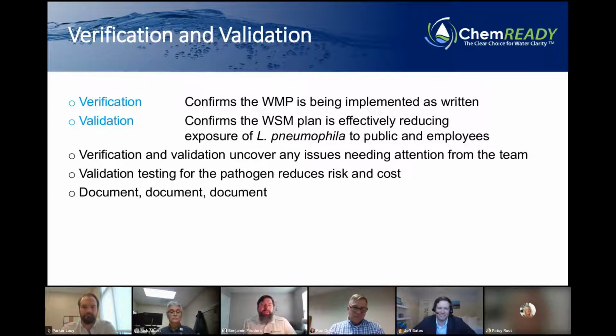That brings us to verification and validation. I wanted to remind everyone what that means. In ASHRAE 188, there's a required verification and validation step, so we'll talk about best practices here. The verification step means the water management plan is being implemented as written, so it conforms to the requirements of ASHRAE 188. This is typically done through audits and reviews, whether internal or through a third party.